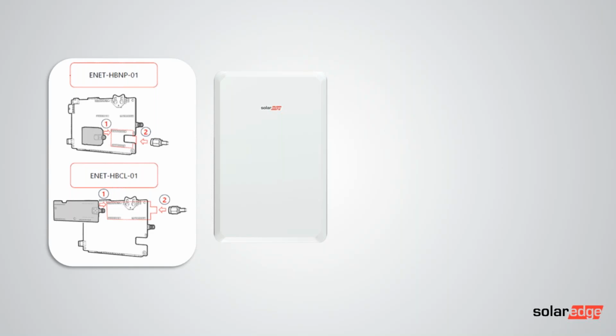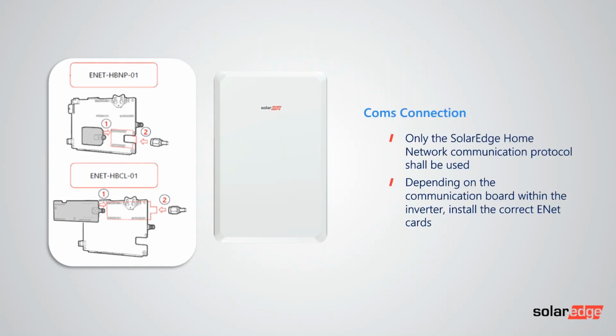Also, as Doug mentioned, EnergyNet is the mandatory communication protocol. What is really important is to understand the fact that the residential three-phase inverters may have two different communication cards in them. So one has a single comms board slot on it, and the other one has two. Because of that, there are two different EnergyNet cards. As you can see there, one is the EnergyNet or ENET HBNP-01, and the other is the HBCL-01. The simple way to approach this is if the card in the inverter can take the small EnergyNet card, use that one. If it can only take the big one, use that one.